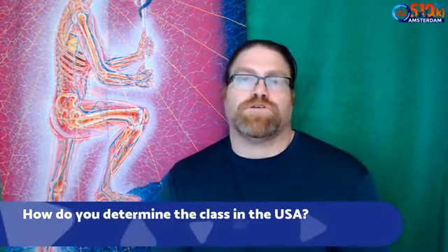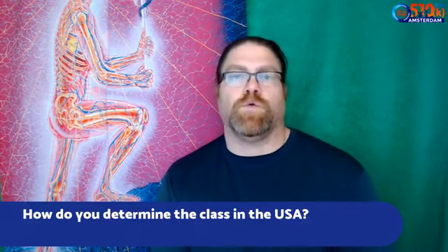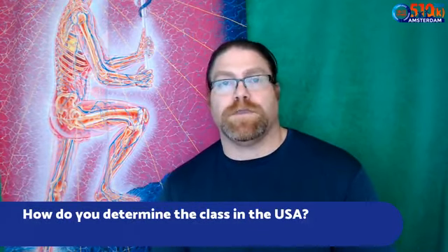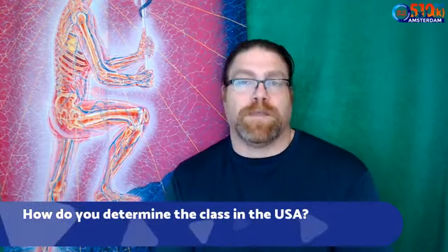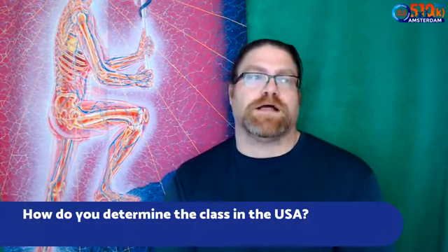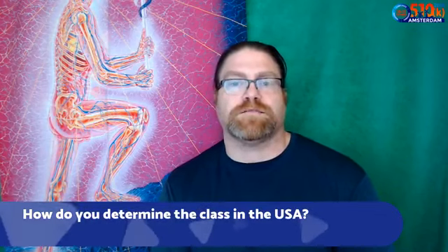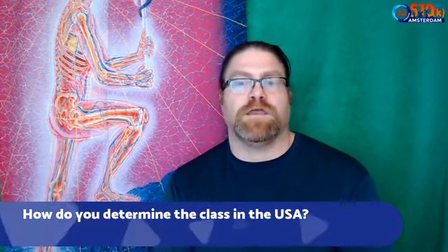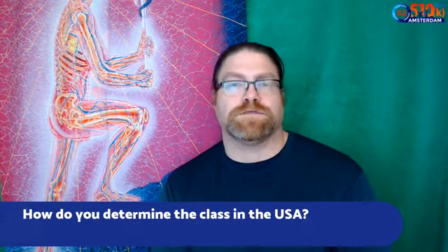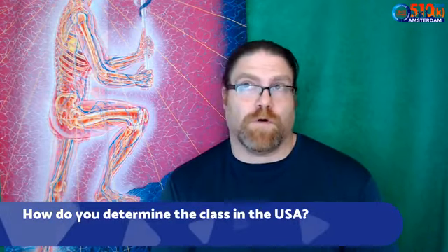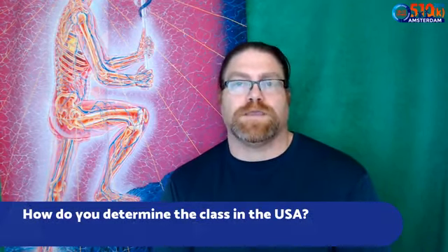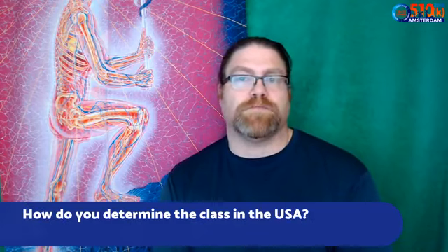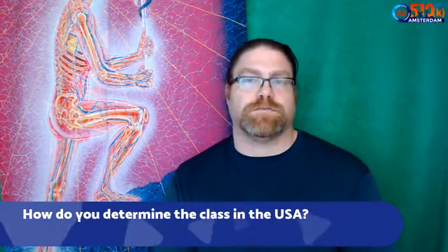So how do you determine what class your product is if you're already CE marked in Europe and you want to submit to the FDA as a 510K? If it's class 2A or class 2B in Europe, is it a class 2 in the US? It depends. And you can't use the risk classification that the Europeans use because that's a rule-based risk classification system, whereas the FDA has product classifications that are based on products that are very similar. So instead of having 18 of the old rules and 20-something of the new rules in the MDR, the FDA has more than 1,000 different product classifications grouped by different products, and some of those are class 2, some of those are class 3, some are class 1.